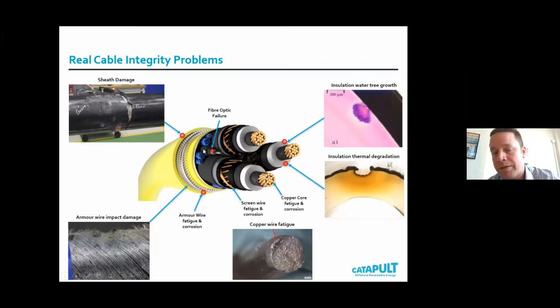Fiber optics, if you damage those, they can actually result in failure of the whole cable. So that's another problem area. Armor wires, steel, nice and robust, but steel still corrodes and it fatigues. So that's another area that can fail. And if you smack the armor wire with a dropped object, an anchor, that can also cause failure of the armor wire. In this case, that's impact damage. And finally, the sheath itself, if that isn't properly designed or it's seeing too much strain, it can also crack and damage as well. And if the sheath damages, that can let water in, which can then cause problems with the other components in terms of corrosion.